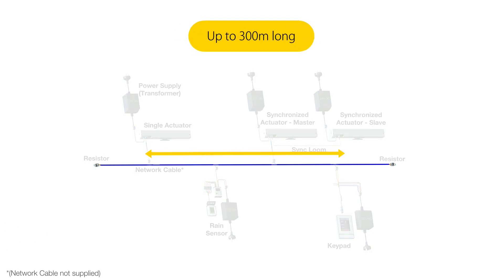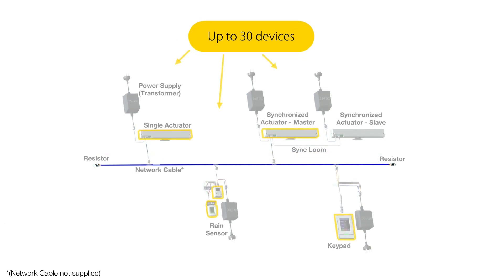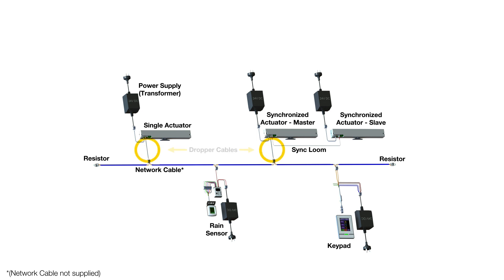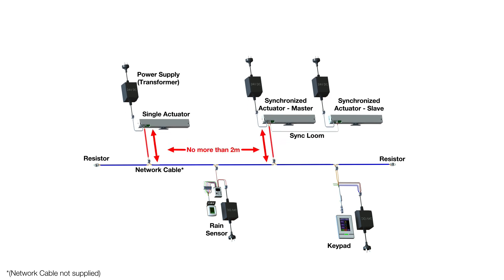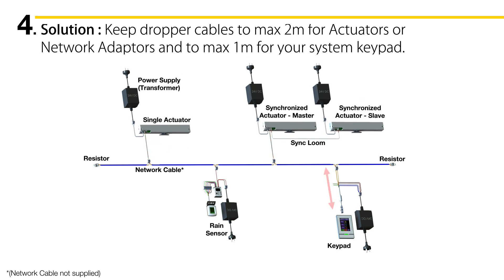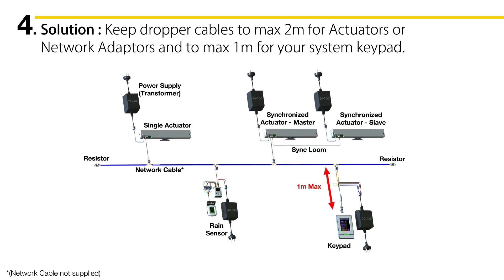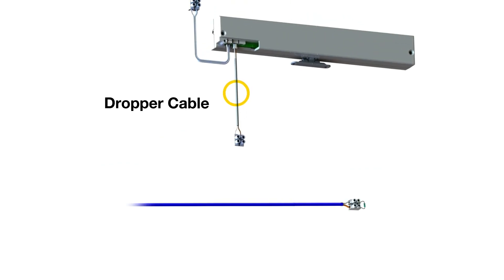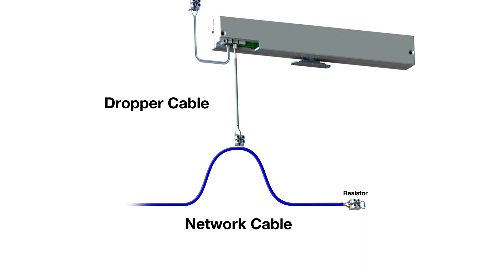The main network cable can be up to 300 metres long, and you can connect up to 30 devices to it. It's a good idea to plan your main network cable run so that the dropper cables to each device are as short as possible, as dropper cables that are too long will cause data corruption. Where a dropper cable connects an actuator or network adapter, it must be no more than two metres long. Where the dropper cable connects to a keypad, no more than one metre. If you have trouble getting the provided dropper cables to reach the network cable, simply loop the network cable closer to the device.